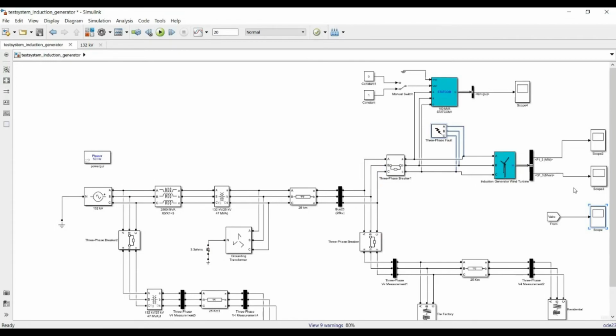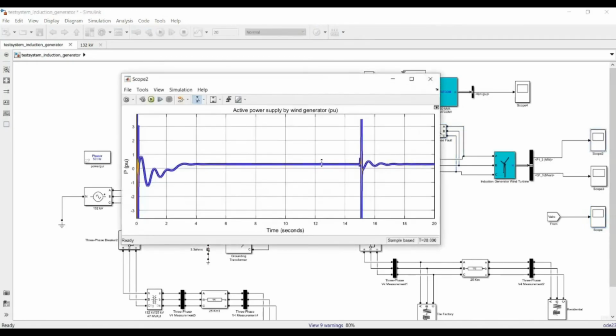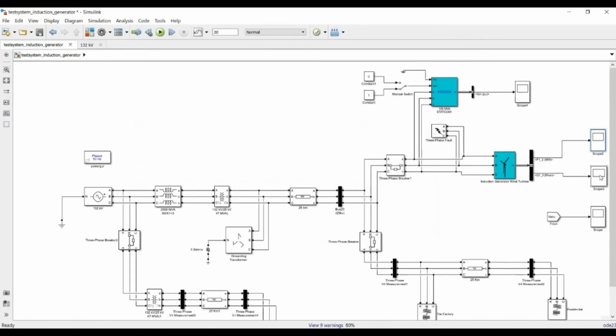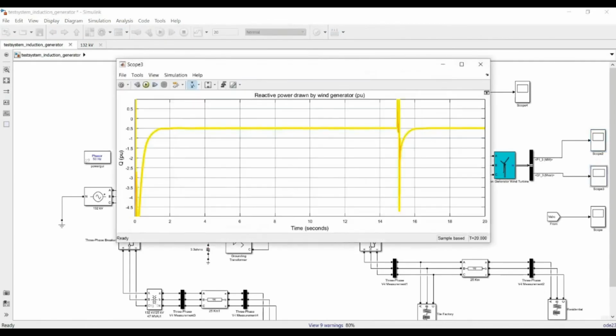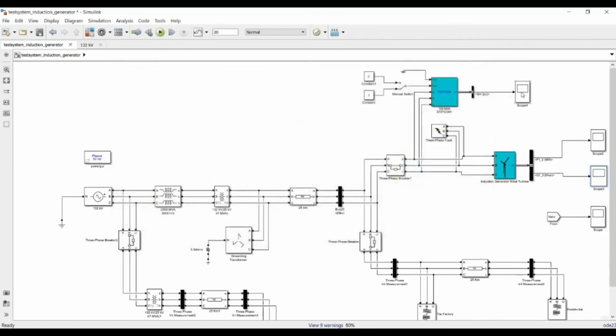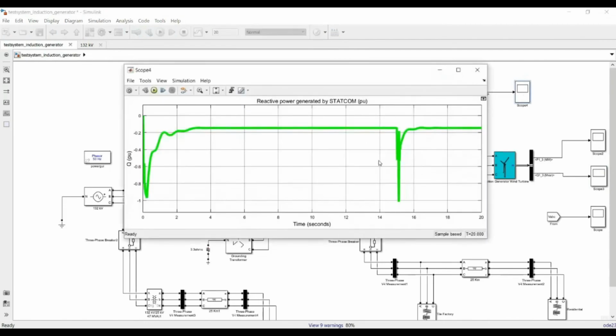Besides voltage, we can also see the active power supplied by the wind turbine, and when the fault occurs we can also see the reactive power drawn by the generator, and the reactive power generated by the STATCOM.